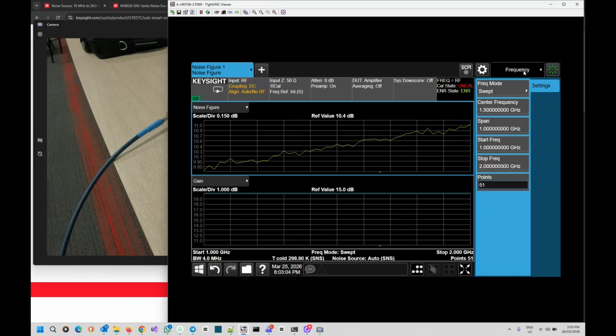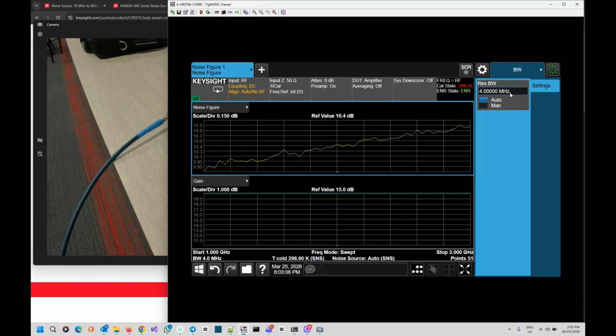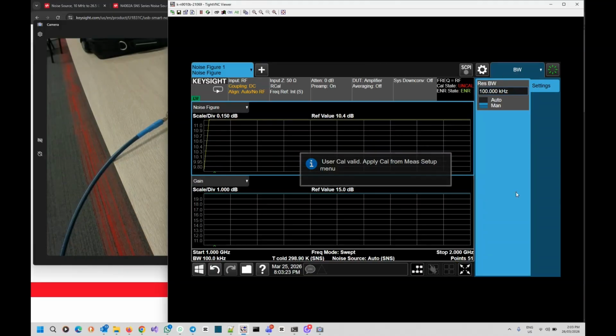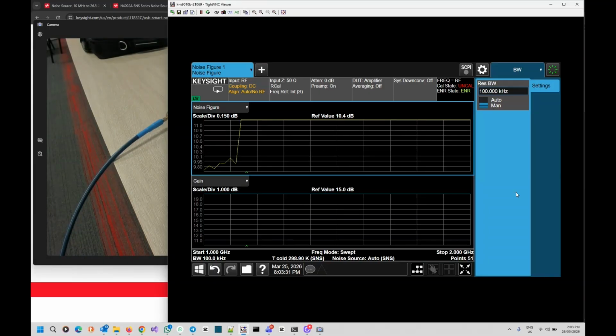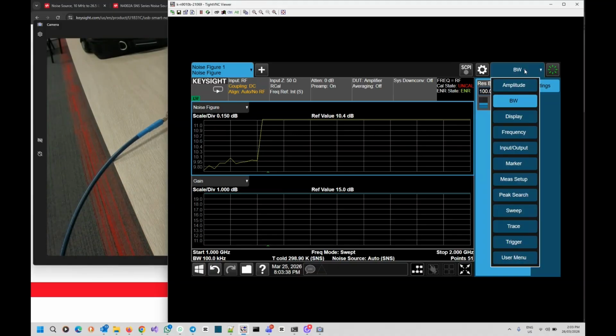The next thing I want to do is change the resolution bandwidth. Currently we have 4 meg. It's wide open, there's a lot of noise coming in, a lot of fluctuations happening. For calibration purposes, normally I'll go with something very narrow. Let's start with 100K. Even at 100K, you see that it takes a long time to sweep through because at every point the filter has to stabilize and do the measurement. While it's doing its thing, let's go to measurement setup.